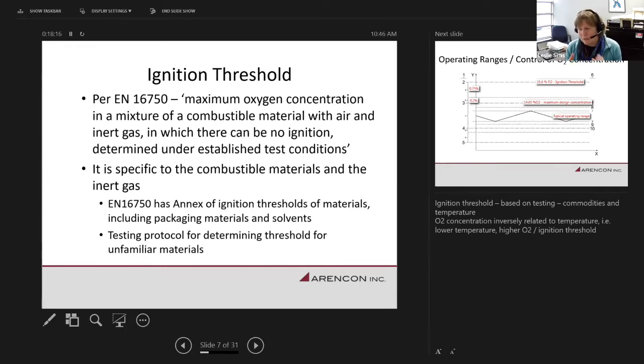So I believe that the fire performance is similar, in that we don't see fewer fires at high altitude because we have less oxygen. They still will have fires in those environments. So the hypoxic fire prevention system will still work because it's reducing the oxygen level by the introduction of nitrogen. So it's a normobaric hypoxic environment that you create within these systems or within these protected areas, whereas at high elevation, it's hypobaric. So you're kind of coming at it from two directions. I don't know the answer with respect to the impact on people because in a sense you're creating an oxygen reduction from two directions. But I believe from a fire standpoint, the behavior is exactly the same.